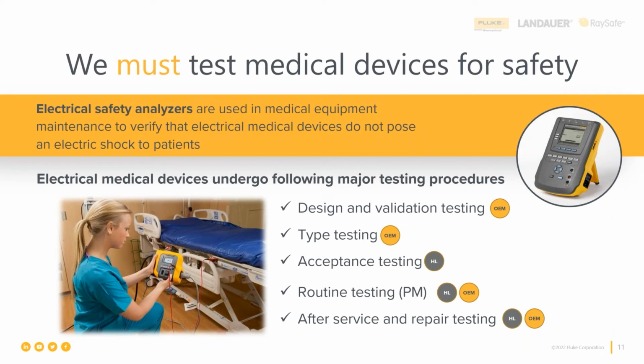So let's talk about some situations. If we are working for the manufacturer of a medical device, then electrical safety needs to be done during the design validation of a new product that they're going to put out on the market, and they need to verify that it's not going to cause too high a leakage current to begin with. That's also called type testing. And then also in their final assembly test in the factory, electrical safety testing needs to be done, because that's the first time that all of the parts, the sub-assemblies and components are assembled into one medical device. And so each one of those needs to be tested for electrical safety in the final assembly test in the factory.